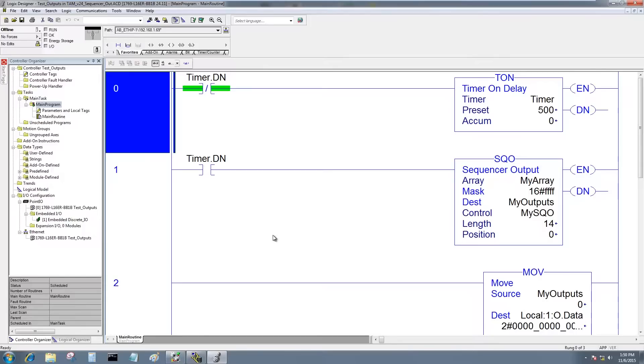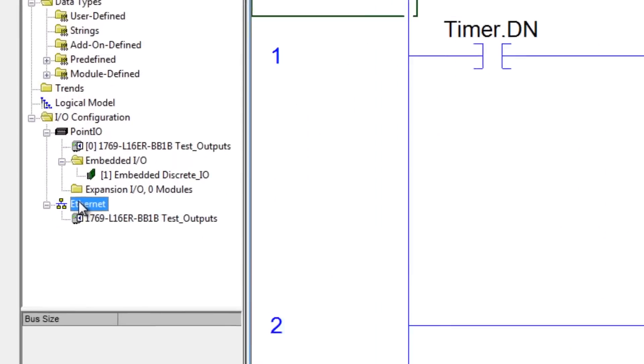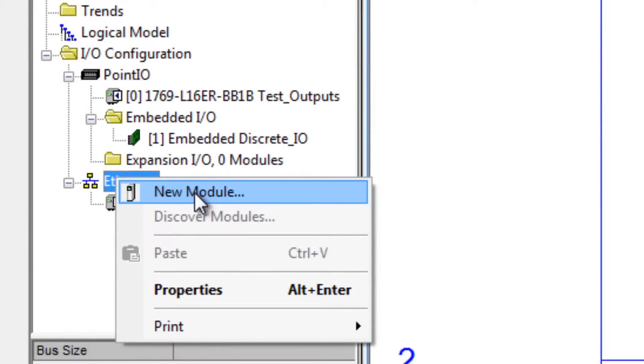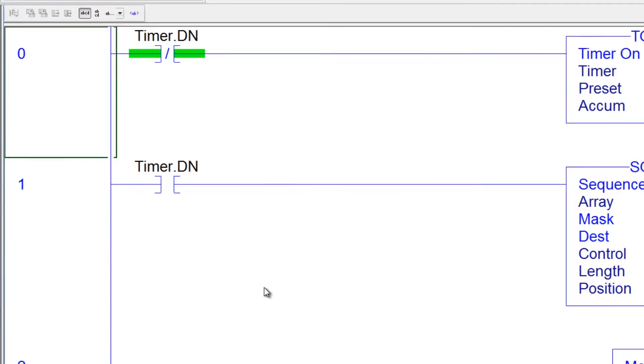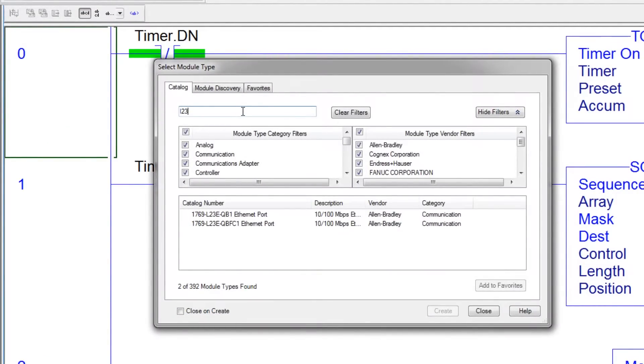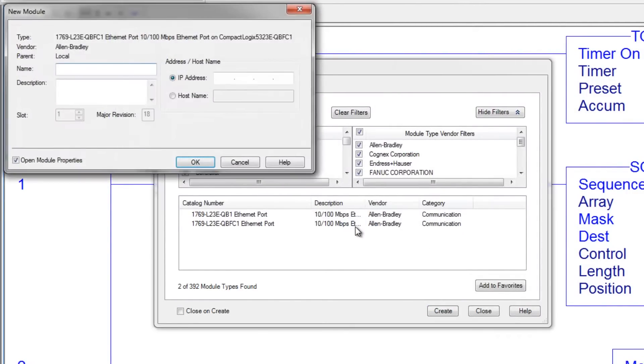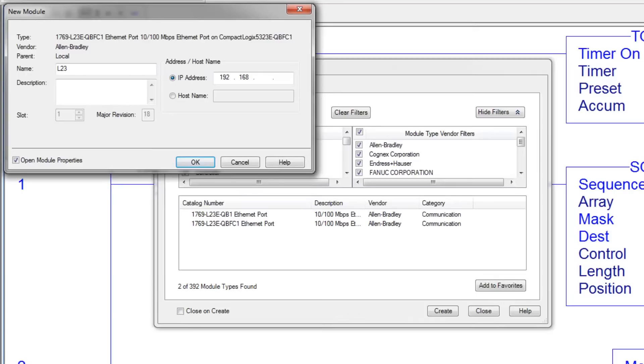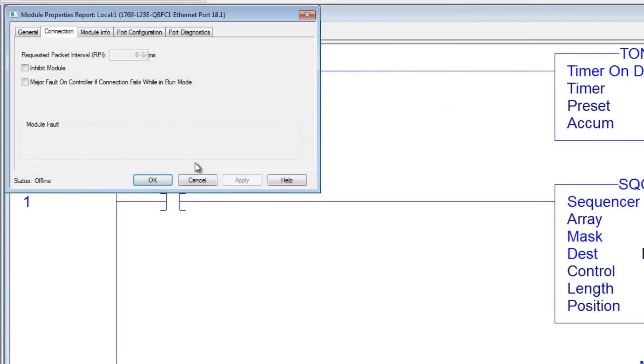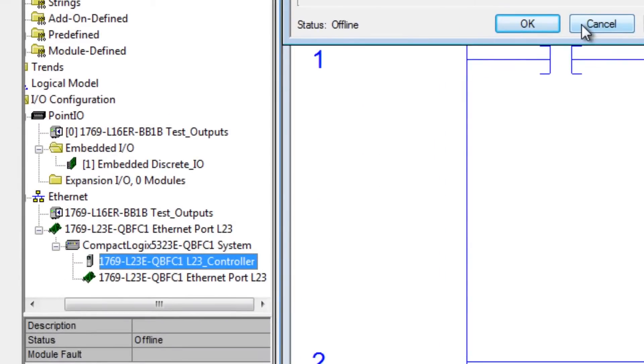So the first thing we're going to do is add the L23 to the L16's program. I'm going to come down here on the Ethernet, right click and do new module and here I'm just going to type in L23 and hit create. It's version 18 so I'll go ahead and select version 18. It's asking for a name. I'm just going to call it L23 and I just happen to know its IP address is 192.168.1.68. Let's go ahead and hit OK. And there it is.